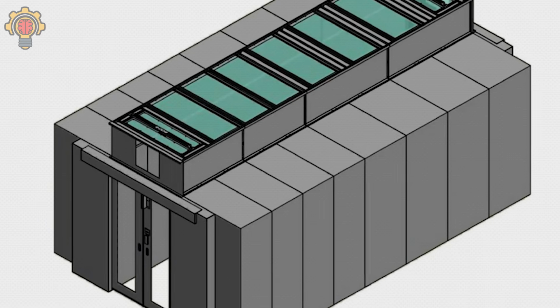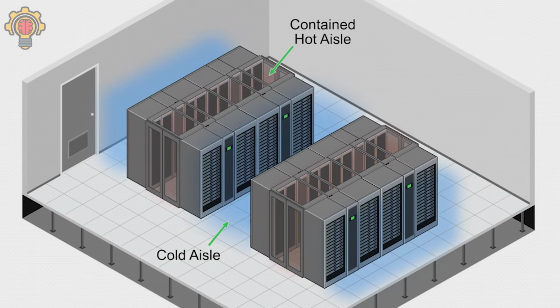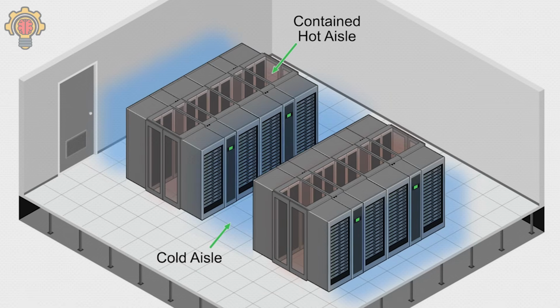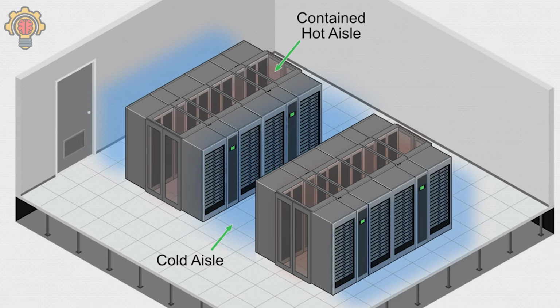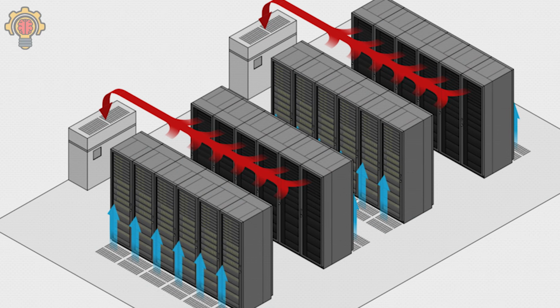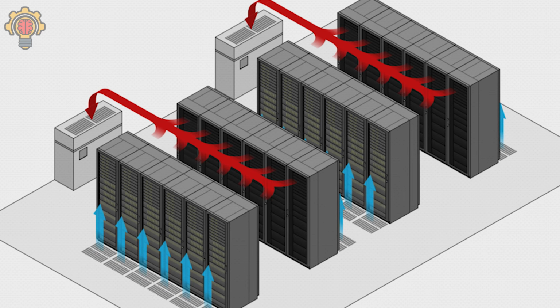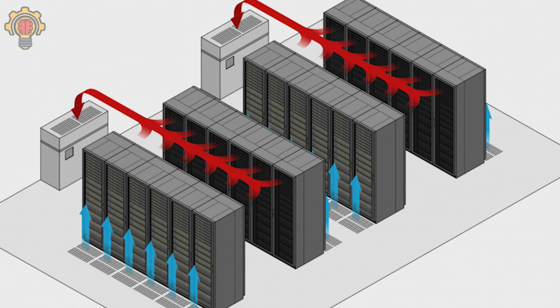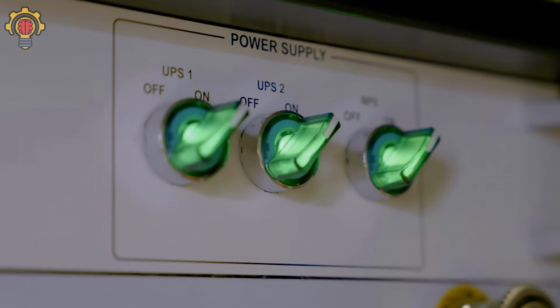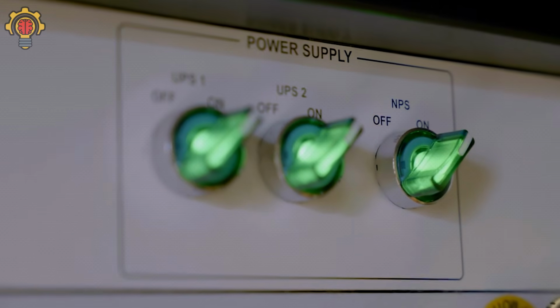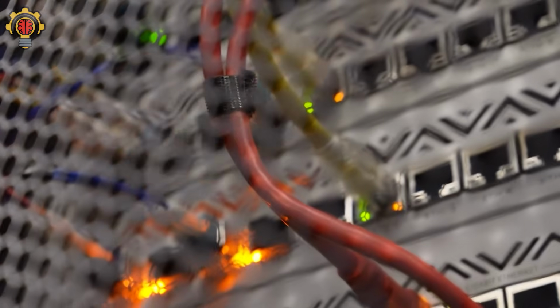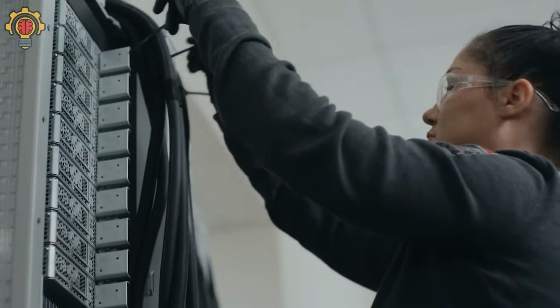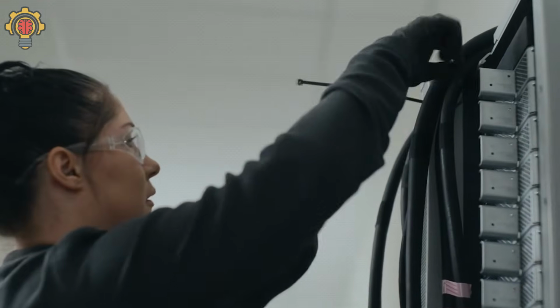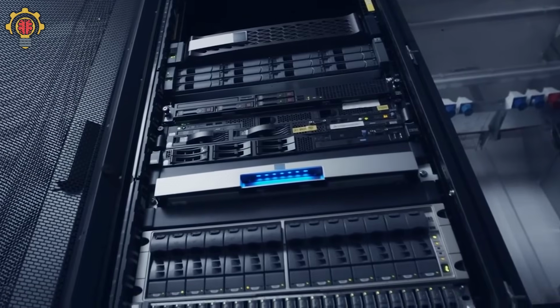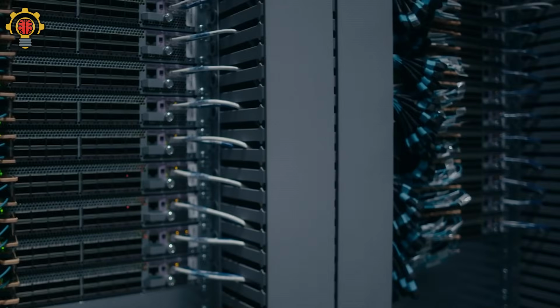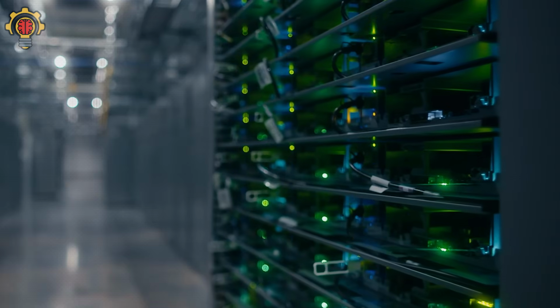In a hot aisle containment system, or HAC, the hot exhaust air is enclosed instead, then removed directly back to the cooling equipment. Both methods dramatically improve efficiency because hot and cold air no longer mix together. Servers receive more stable temperatures, cooling units work less, and energy consumption drops significantly. But even these advanced airflow systems began reaching their limits. Because modern workloads, especially AI computing and cryptocurrency mining, generate unbelievable heat densities, some server racks now produce so much heat that ordinary air cooling simply cannot remove it fast enough anymore.